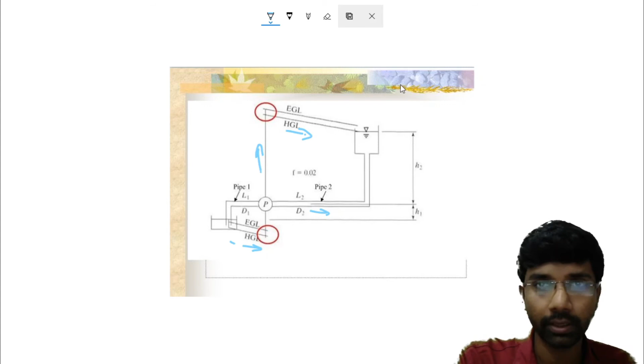As long as the fluid is flowing in this pipe, your hydraulic gradient line gets reduced, and whenever the fluid reaches the pump, it will give a lot of energy to the fluid, so that the total energy and hydraulic energy will move high. At this particular level it will move high, and then the fluid starts flowing in this pipe. Whenever it is flowing in this pipe, obviously due to the frictional losses, hydraulic gradient and energy gradient will get reduced, right? Hope you people are getting the concepts.